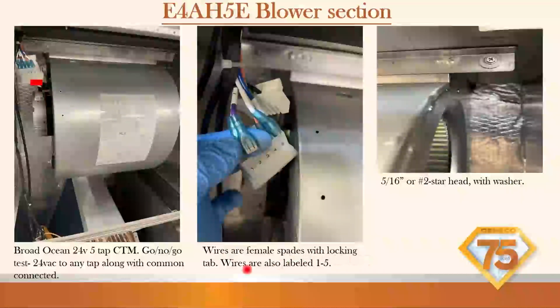Wires are female spades with locking tab. That's important, because if you go to try to pull that out, it's going to be locked in there. So you're going to have to stick your thermostat flathead down in there. You might break the wire if you're just trying to pull on it. So keep that in mind. Everything's nicely labeled. Wires are also labeled 1 through 5. You've got a 5/16 with washer holding that blower in. So it's going to be on both sides. You've got 2 screws, remove those, and the blower section is going to come out. Easy.